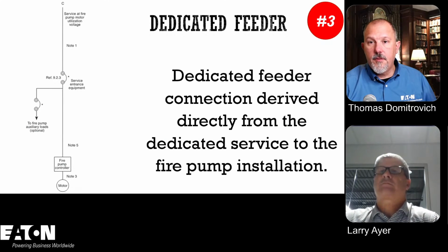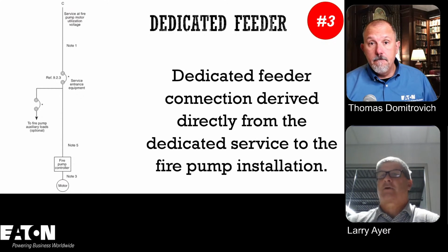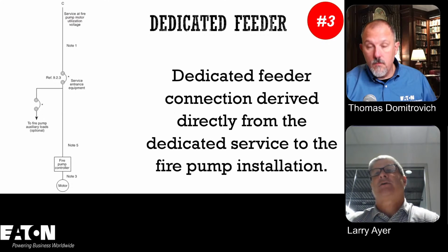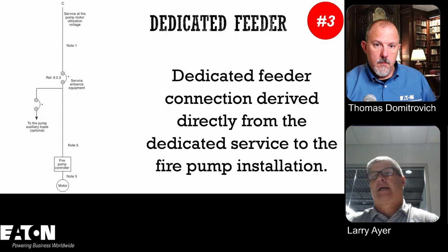Yep. And then there's number 3, which is a dedicated feeder. Now, when you say feeder, it's not a service. So this feeder is coming from another piece of equipment, right? That's correct. So basically number 1 is kind of coming from the service straight into the fire pump, or going into that switchboard and going straight to the fire pump.